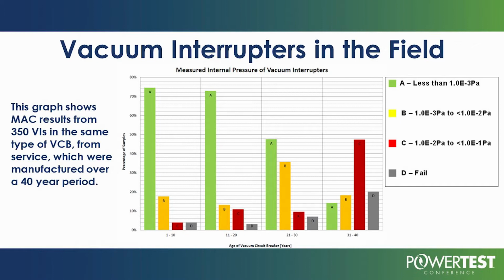Some of these interrupters, as you can see here, and these circuit breakers were 1 to 10 years old, some 10 to 20, some 20 to 30, some 30 to 40, and you can see the failure rate of simply doing an AC withstand test for these breakers changes dramatically. You can also see that the ones that are 1 to 10 years old, we found very few failed interrupters. We found very few high pressure interrupters when using magnetron testing. When you get to 20 to 30, 30 to 40, you can see the failure rate accelerates dramatically.